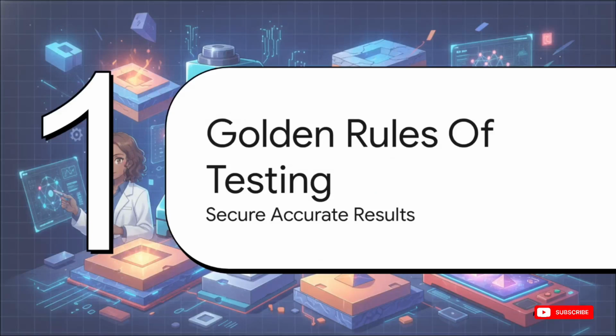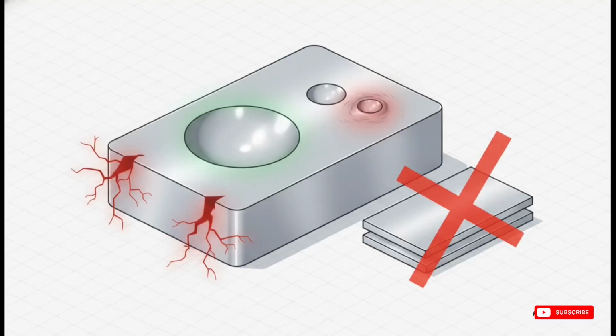Moving to our final part, Section 6, Golden Rules of Testing, Securing Accurate Results. Regardless of which method you choose, you have to play by the rules of the game to avoid collecting completely useless data. Here are the non-negotiables. First, your metal specimen must be at least 10 times thicker than the depth of the dent. Otherwise, the hard anvil underneath will actually artificially inflate your reading. Second, you cannot test too close to an edge or closer than 3 diameters to a previous dent. Why? Because that localized plastic deformation we talked about earlier actually work hardens the metal right around the dent. If you test too close to an old dent, the metal there is artificially harder and boom, your results are ruined. Finally, your surface must be perfectly smooth and flat, and you should literally never, ever stack specimens on top of each other during a test.